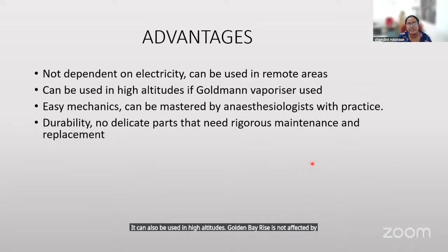A Boyle's machine is pneumatically driven, it's mechanically driven, it is not dependent on electricity. So it is useful in remote areas where there may be other resource issues. It can also be used at high altitude, as the Goldmann vaporizer is not affected by altitude change. Unlike other vaporizers, which we must calibrate according to the altitude or the height.